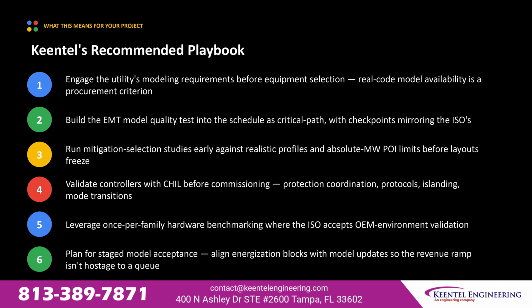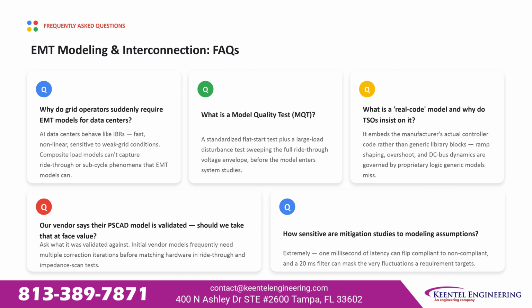4. Validate controllers with controller hardware in the loop testing before commissioning, covering protection coordination, communication protocols, islanding, and mode transitions. 5. Leverage once-per-family hardware benchmarking wherever the ISO accepts OEM environment validation. And 6. Plan for staged model acceptance, aligning energization blocks with model updates so the revenue ramp isn't held hostage to a queue. A few questions we hear often.